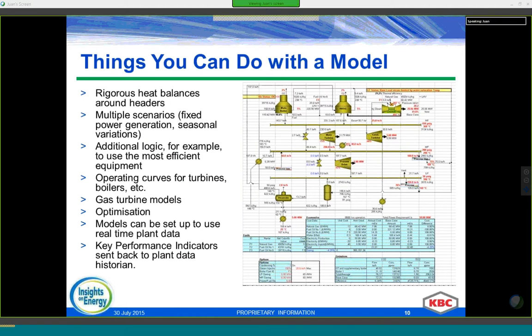In terms of what we can do with the model: first, we can develop a heat and mass balance around the headers, which helps determine losses and any metering issues. If the model is connected to a data historian, it can be used for monitoring and tracking performance, and to determine lost opportunities — for instance, if steam is being let down by a letdown valve instead of passing through a turbine to generate power. We can also use the model to calculate the real value or price of steam and the real impact of projects — from an economic standpoint but also in terms of how they affect the overall site steam and power balance. We can test multiple operating scenarios, perform what-if analysis, review benefits of quick wins and investment ideas, and perform optimization of current operation.